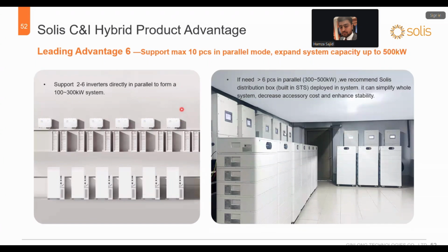These industrial grade inverters can be easily paralleled up to 10, okay, to support a 500 kilowatt site. So if you are going to install 2 to 6 inverters, you can install them directly with the system. But if you are exceeding 6 pieces, you need to install the STS to make sure that you can get a stable power.